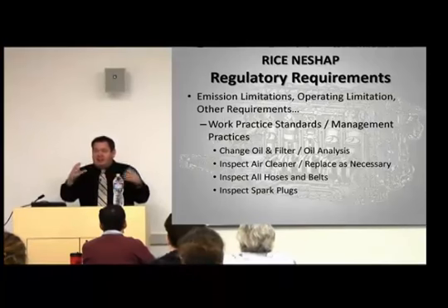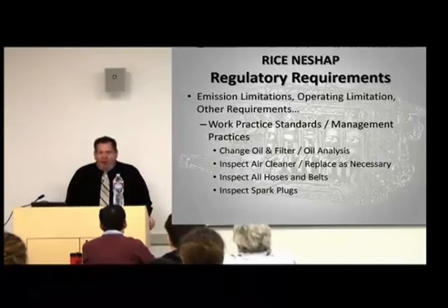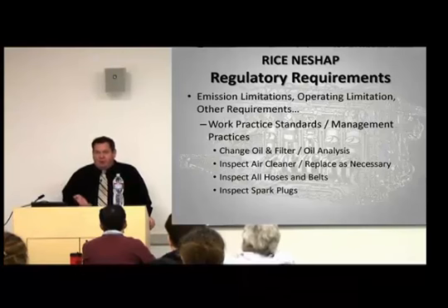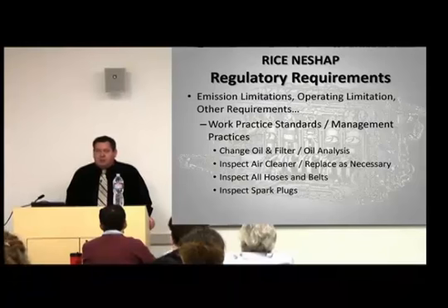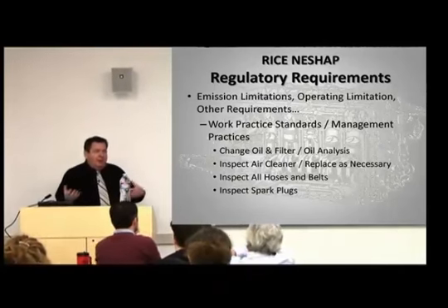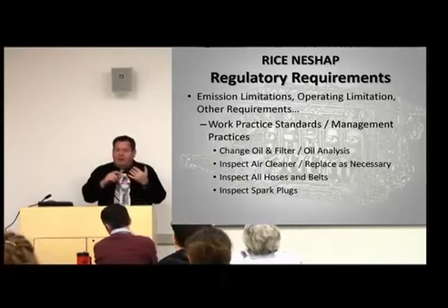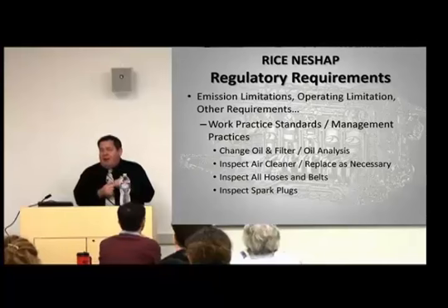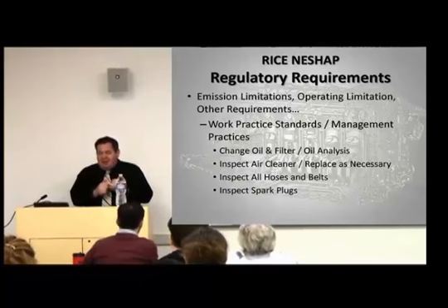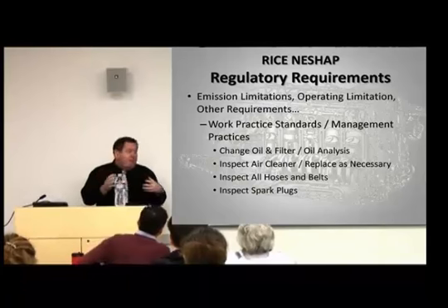Well, lots of engines, these crankcase gases go back into the engine to be reburned, recirculated. And so it's going to bias your air-fuel mixture. And if you bias your air-fuel mixture richer than was designed by the manufacturer or richer than designed by the emission limits, you're going to increase your emissions. So it makes sense to incorporate that you change oil and filter periodically to keep this from happening. So they have management practice standards or work practice standards that say, yeah, some engines it's every 500 hours, some engines 1,000, some engines 1,440, and some engines 4,320 hours. All depends on the engine.